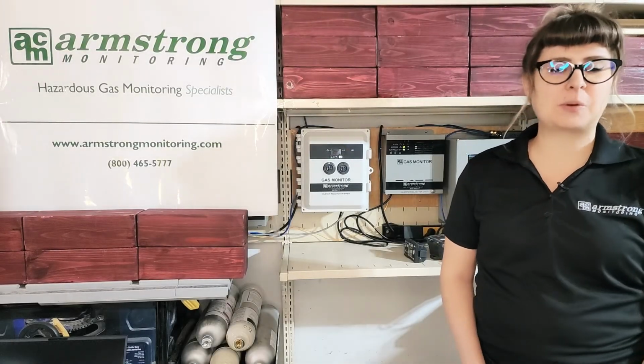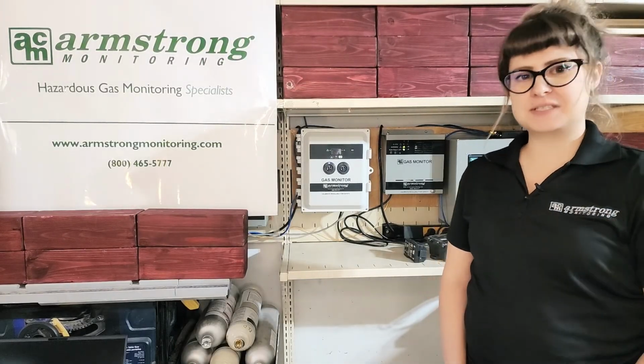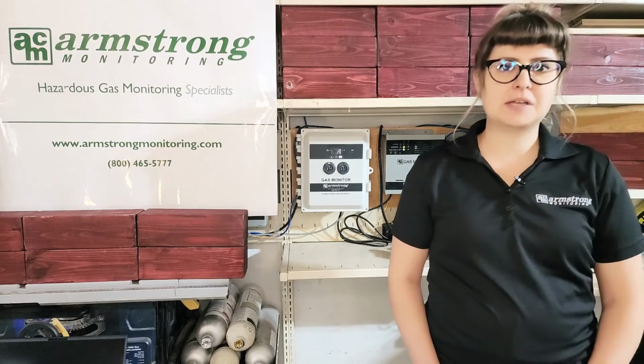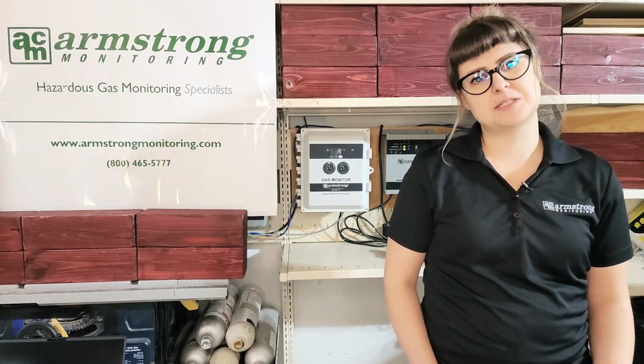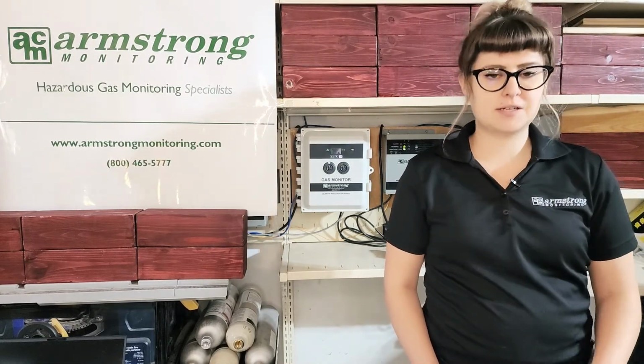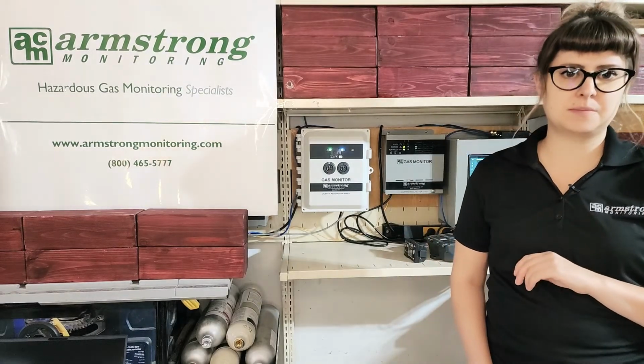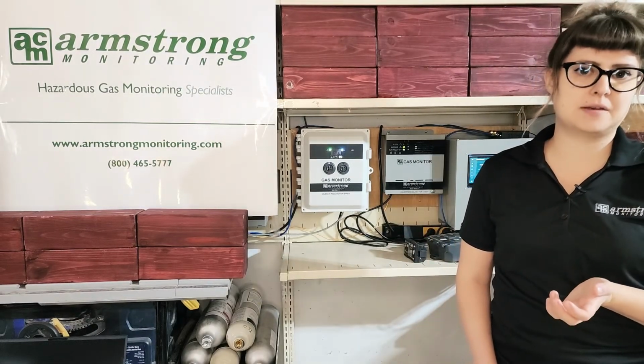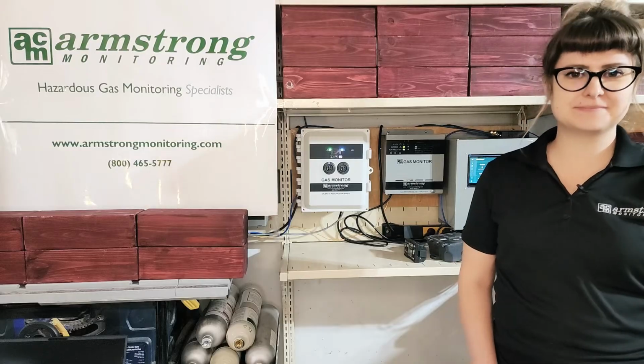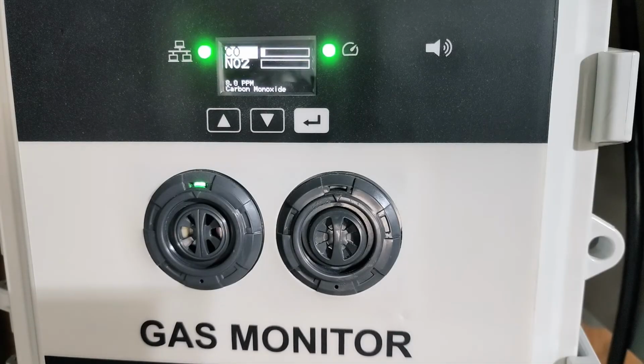At this point, if you're working with an AMC-1B VC, you can move on to calibrating the NO2 sensor using the same steps we used previously. This time selecting the NO2 sensor in the menu and using NO2 span calibration gas. After the unit's been successfully calibrated and it has exited warm-up mode, both the network status LED and the sensor status LED should be green, and the gas concentration is shown on the display.